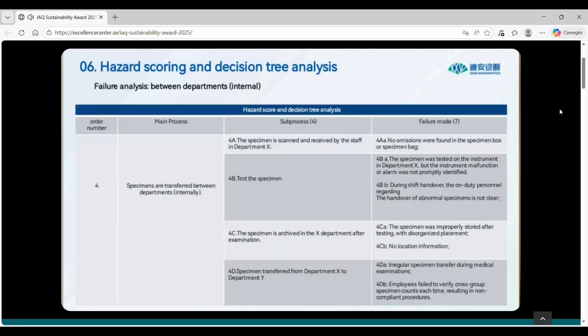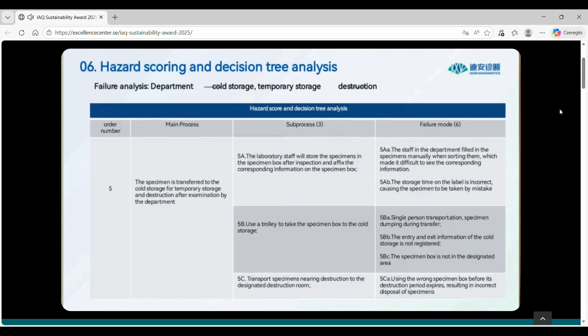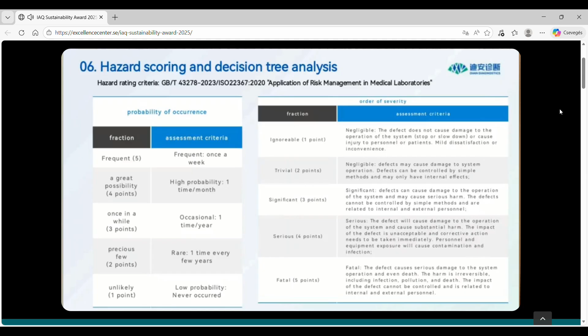So what should we do about these 27 modes of failure? Don't worry, the quality tool hazard score and decision tree analysis point the way for us. The first is the hazard score. Based on the document application of risk management in medical laboratories, we established hazard scoring criteria focusing on 2 dimensions: probability of occurrence and severity. The hazard value is calculated as probability of occurrence multiplied by severity, similar to traffic signal color codes.